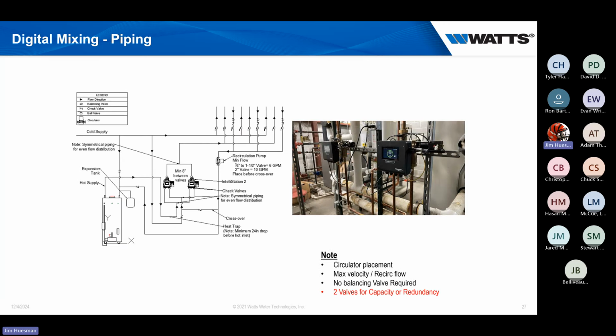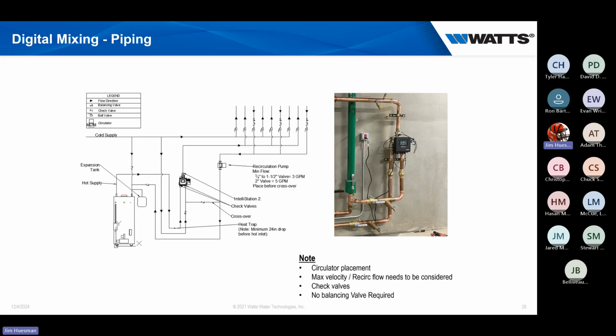Now we jump into, we have a valve here, but say we're going to act like this is a large 2-inch valve. We decided to go with 2-inch because, like everything, we've got to hit flow rates. We need to know what's going on. So we'll take our fixture count, add it to a Hunter's curve, and find out what we need to do to really get this working where we want.